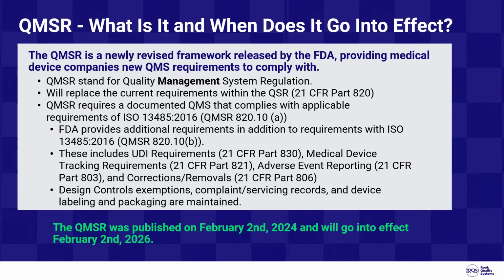The FDA does provide additional requirements, so it's not just 13485 certification or compliance and you're good to go. There are additional requirements that you have to meet for UDI, which is in Part 830, medical device tracking, if it applies to your device, in Part 821, adverse event reporting, which is covered in Part 803, and corrections and removals, which are covered in Part 806. None of these are new requirements. These are things that medical device manufacturers have had to do anyway. The new QMSR is just going to explicitly point you to these different sections of 21 CFR.